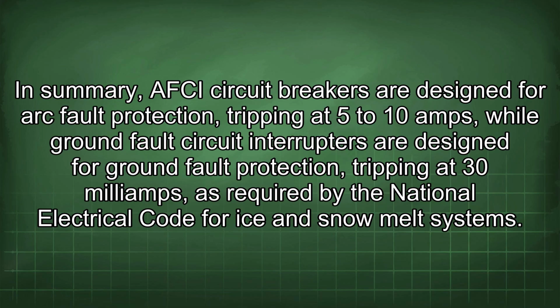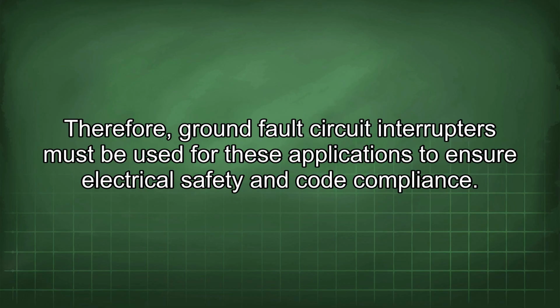In summary, AFCI circuit breakers are designed for arc fault protection, tripping at 5 to 10 amps, while ground fault circuit interrupters are designed for ground fault protection, tripping at 30 mA, as required by the National Electrical Code for ice and snow melt systems. Therefore, ground fault circuit interrupters must be used for these applications to ensure electrical safety and code compliance.